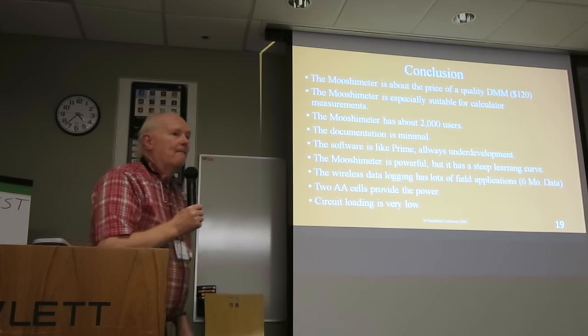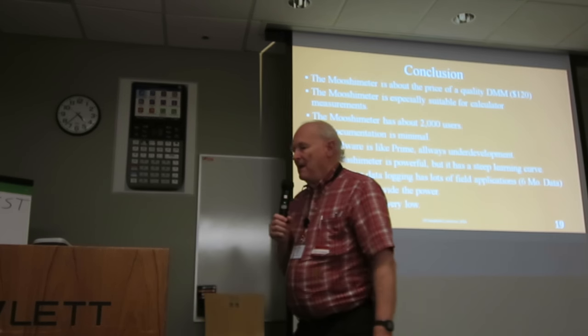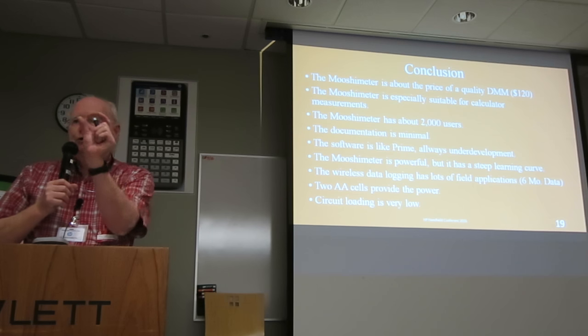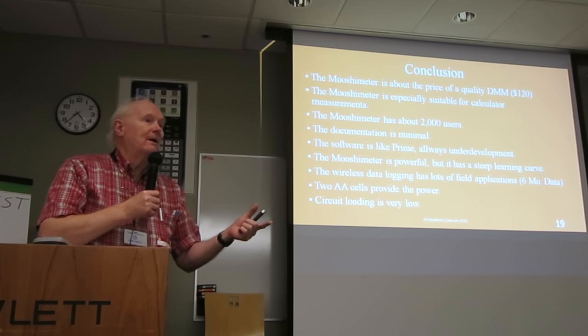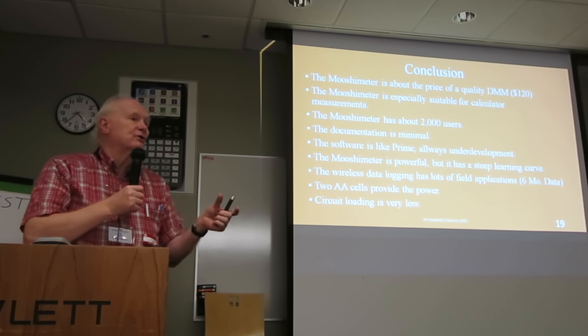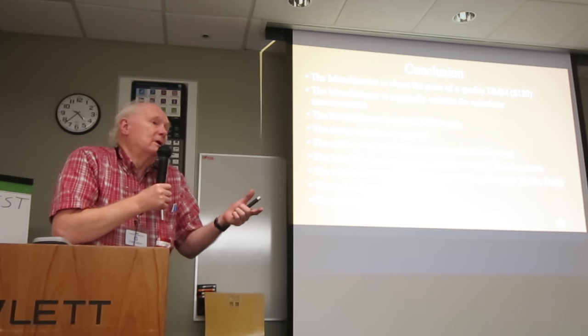Question: What is its frequency response? Looking at the specs, it's one kilohertz — not real high. From my experience with a function generator, the idea is that you can take the two data channels and measure power factor, power, and distortion. There's a lot of things you can do, but it's not a fast device. We're talking about an electrocardiogram front-end, so maybe four or five hertz biologically speaking — it's just not a high-speed device.